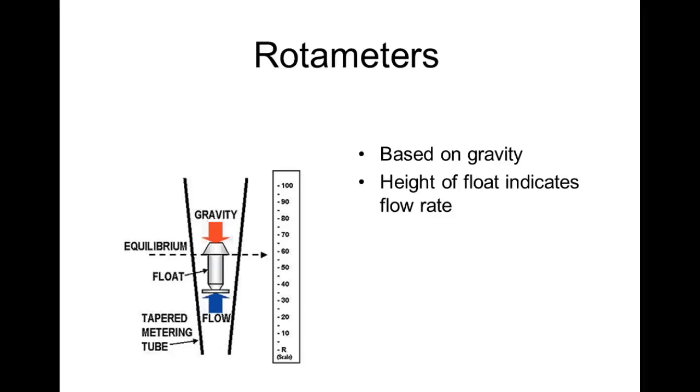This is a rotameter. So on a rotameter, what we do is we use gravity. These things mount vertical. And then we put flow through here, right? Y'all understand that? And then this is calibrated. It's perfectly sized. It's machined, and it has a precise weight. And what it does, depending on the amount of flow, is where the weight of the instrument is going to do what? Match the weight of the flow, or how much it's pushing against there.